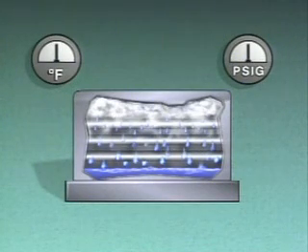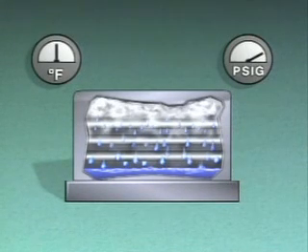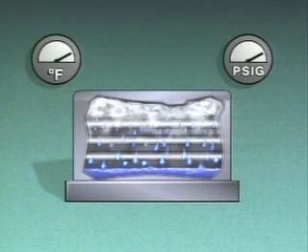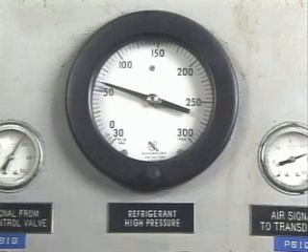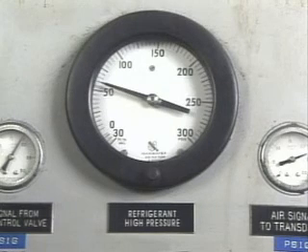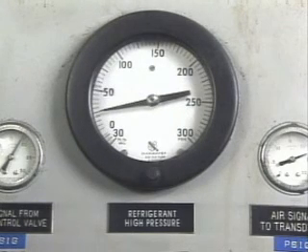Pressure has a similar effect on condensing temperature. When the pressure is increased, steam condenses at a higher temperature, and when the pressure is decreased, steam condenses at a lower temperature. The same effect occurs with refrigerants in refrigeration systems. When the refrigerant is at a higher pressure, it boils or condenses at a higher temperature. When the pressure of the refrigerant is reduced, it will boil or condense at a lower temperature.